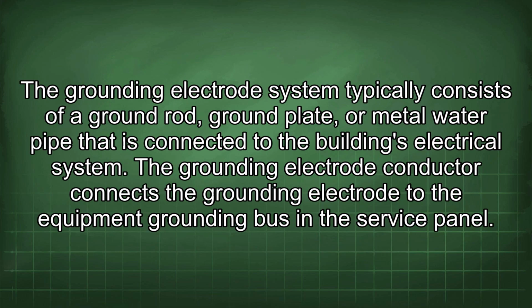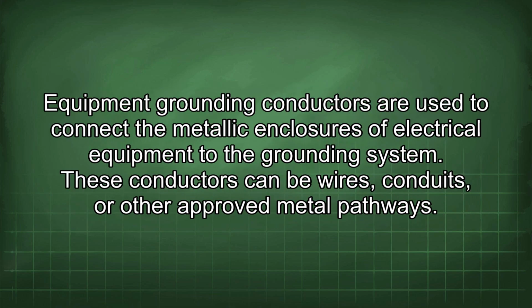The grounding electrode system typically consists of a ground rod, ground plate, or metal water pipe that is connected to the building's electrical system. The grounding electrode conductor connects the grounding electrode to the equipment grounding bus in the service panel. Equipment grounding conductors are used to connect the metallic enclosures of electrical equipment to the grounding system. These conductors can be wires, conduits, or other approved metal pathways.